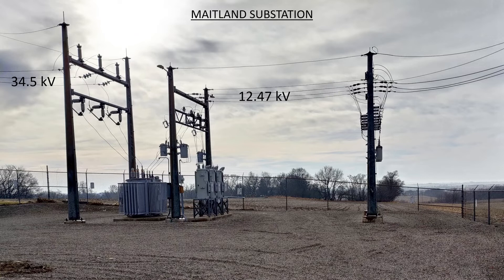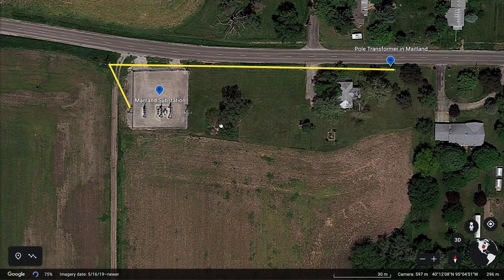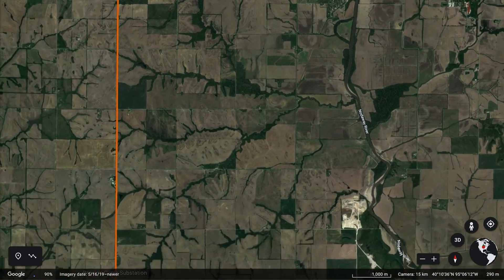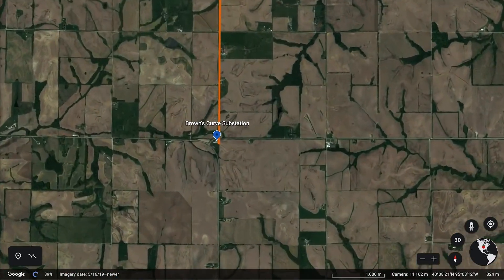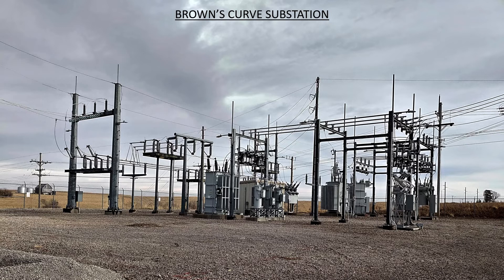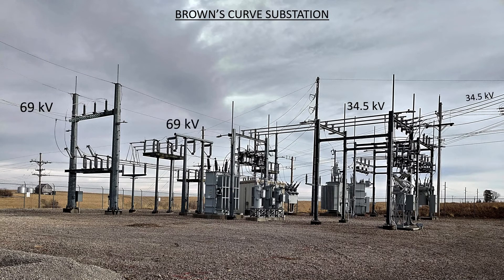I can tell the secondary side apart from the primary side because the primary side of the transformer has larger bushings and the power lines are further off the ground. Where do these 34.5 kilovolt lines come from? If we go west along highway C and then south along highway D a few kilometers, that will bring us to the Browns Curve substation at the junction of highway 113. This is a bigger substation. The secondary side is at 34.5 kilovolts and the primary side is at 69 kilovolts. Again, it's easy to tell them apart because the power lines on the primary side sit further off the ground.